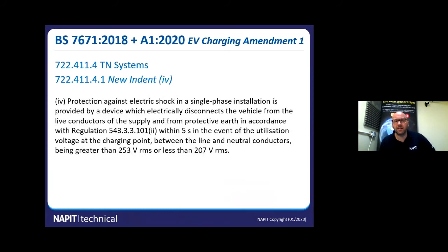So, new indents now. The first one, indent 4: protection against electric shock in a single phase installation is provided by a device which electrically disconnects the vehicle from the live conductors of the supply and from the protective earth in accordance with regulation 543.3.3.101 (ii).